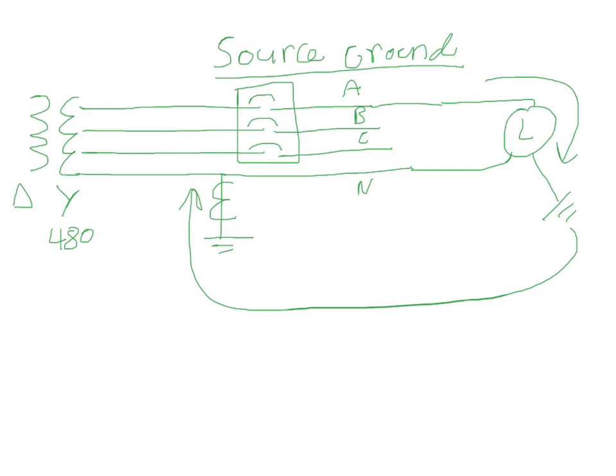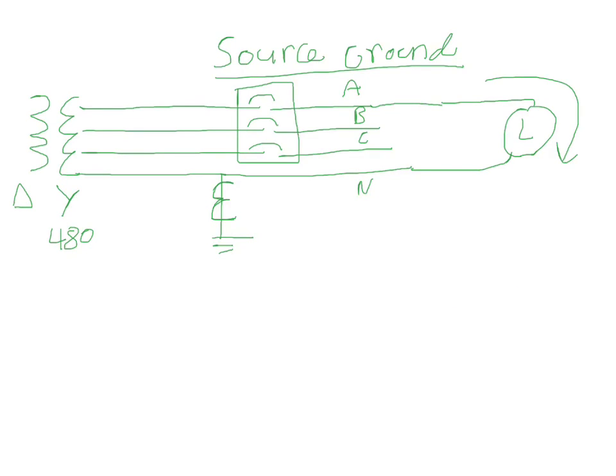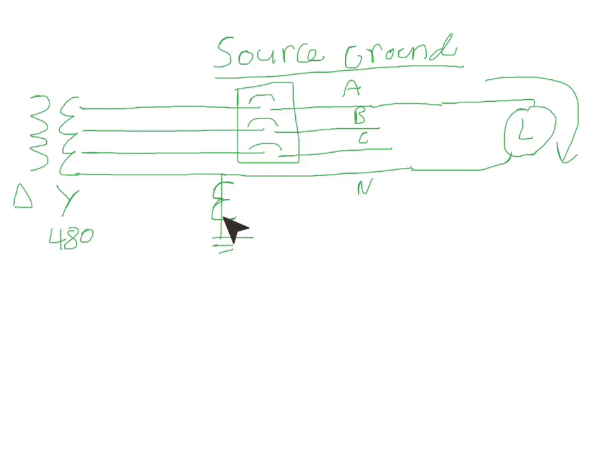Now with that explained, it is very important to keep in mind that the system can't be grounded anywhere else besides where you have the main bonding jumper here with the ground CT on it.